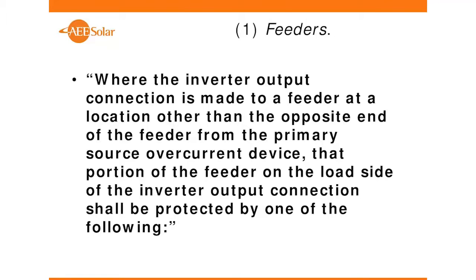And that keeps us from this thing called roundup error, right? When you have roundup error, we're already being very constrained on this 120% rule, and the roundup error can take us right over that 120% pretty routinely. So it's a little more calculation, but it's a lot more accurate, and it lets us put more PV on the same system. So we added feeders and taps, and of course we already had bus bars.